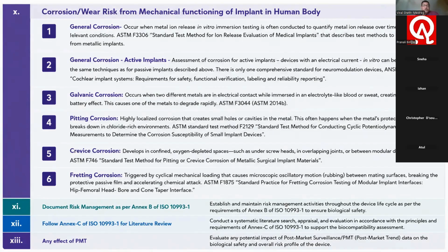device's surface. Active corrosion involves active implants, which require an energy source for the functioning of the medical device. So there is corrosion due to the effect of energy, electricity. For example, the endoscopes that are inserted into the human colon are required to be connected with high radio frequency instrument generators. The manufacturers who only manufacture those electrodes generally say yes, we don't manufacture the instrument. But during clinical applications, your device is required to be connected with the high radio frequency instrument. So it's an active device, and you should also understand the possible risk of corrosion and biological safety of your device in active conditions.